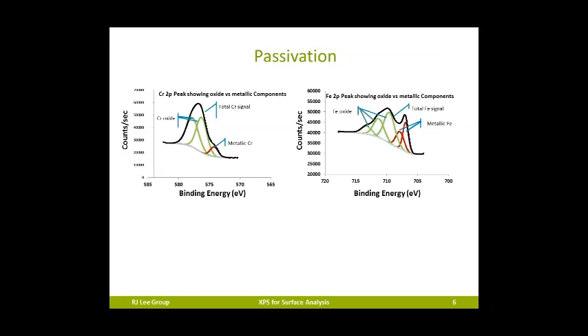In one example, the protective oxide layer on a stainless steel is very thin, approximately 50 atomic layers thick. Few techniques can probe and quantify the composition of this thin skin layer. Non-passivated stainless steel surfaces tend to have non-optimized levels of protective chromium oxide in that skin and have higher iron oxide, which is not protective. The passivation process modifies this native oxide and enriches the chromium and chromium oxide on the very top surface layers, resulting in improved corrosion resistance required for many high-end applications.